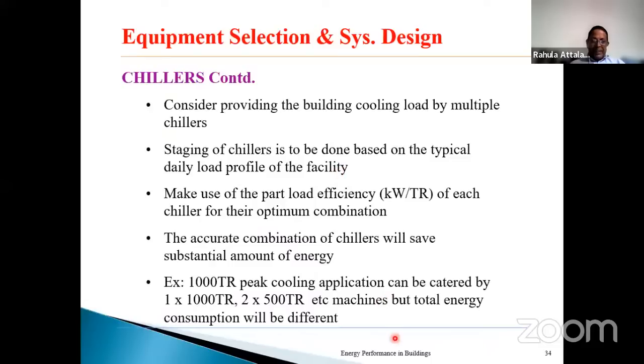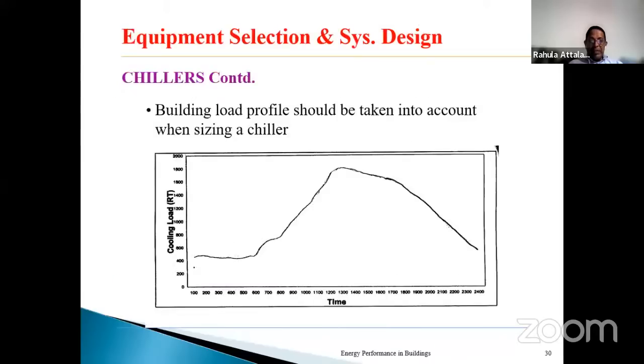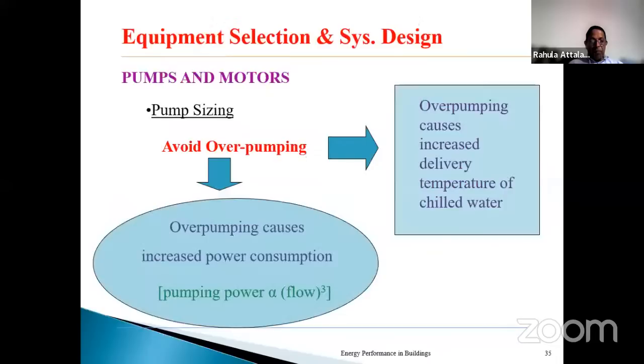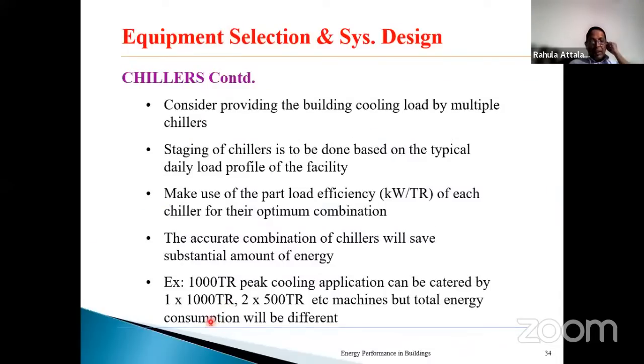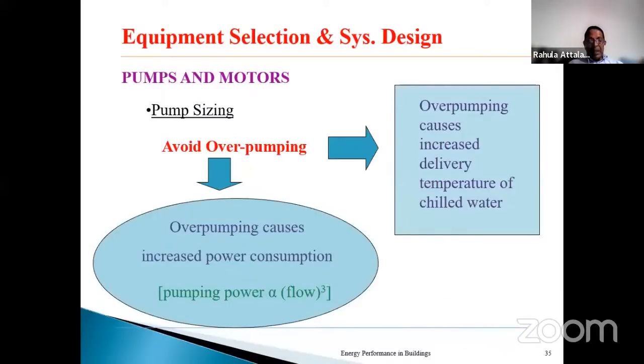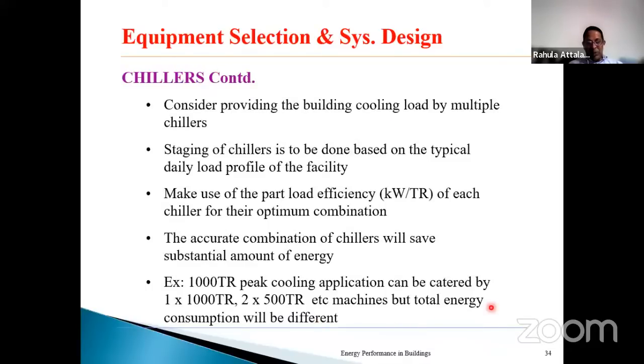Everything depends on the finances, and make use of the part load efficiency, kilowatt per ton. Here there's an example carried out by estimations for you to get an idea. Example: 1,000 tons peak cooling load. In this diagram, assume that this is 1,000 tons. Here it's 1,800 tons. For that example, 1,800 tons, you can have different configurations with a combination of 1,000 ton chillers and 500 ton chillers. Down the line I will show you some results on how the combination is to be taken up.